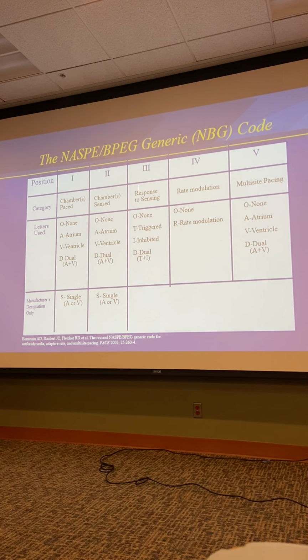So if the spike falls, for instance here, when the ventricle is refractory, it does nothing. If it falls here, when the ventricle can be paced, then you get ventricular pacing. And it is completely regular, and it is completely independent of whatever heartbeats are normally there. So it's asynchronous, it's not sensing anything. And it's intermittently capturing just because of the normal behavior of the heart to be refractory after each beat.